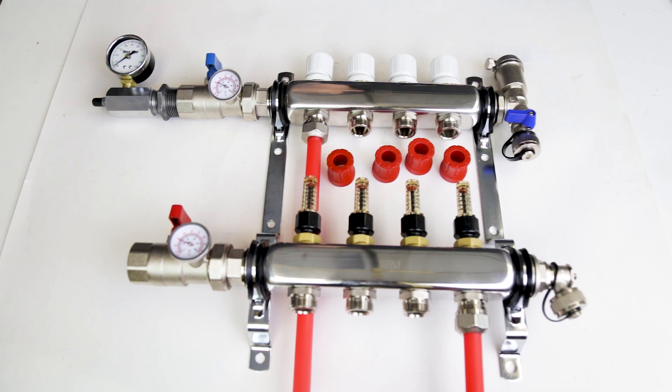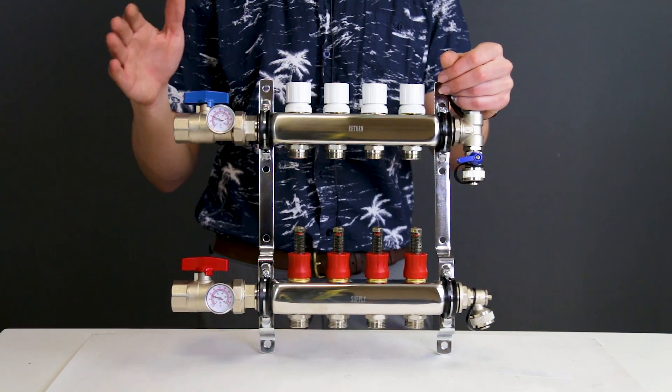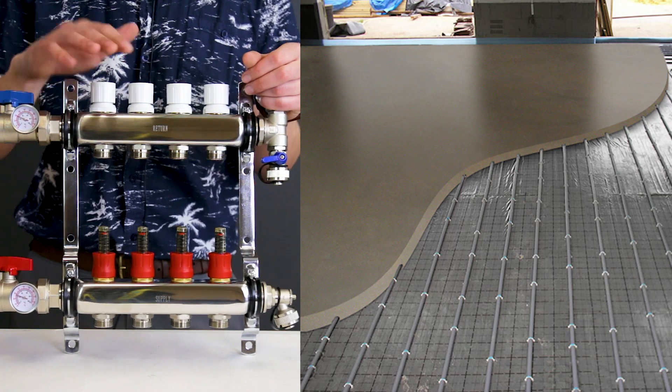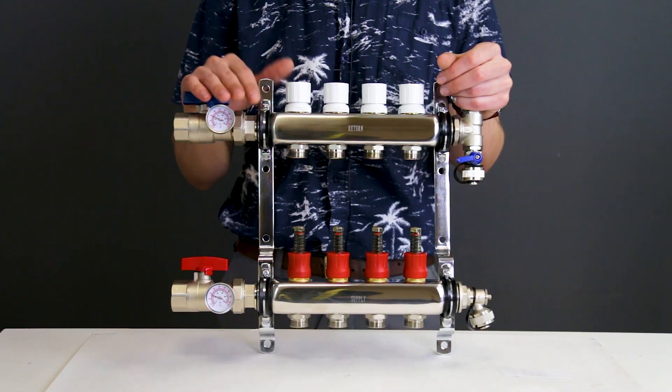If it hasn't dropped, then pump it up to 10 bar and leave it again for 10 minutes. If it stays strong at 10, then you can drop it down to operating pressure between one and one and a half bars. Set the pressure to six bars while you're laying it down underneath screeded floors to prevent damage or collapse in host structure. Once it's been laid and dried, you can go back down to operating pressure.